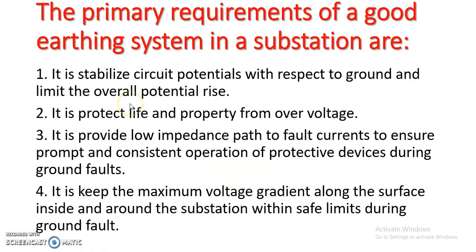Then next, the primary requirements of a good earthing system in a substation. The first requirement is that it stabilizes circuit potential with respect to the ground and limits the overall potential rise. That means with the use of earthing, it will limit the ground potential rise. The second point is that it protects life and property from overvoltage. The third is that it provides a low impedance path to the fault current to ensure prompt and consistent operation of protecting devices during ground fault.